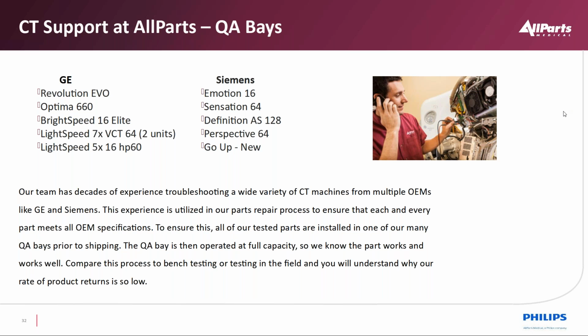And all parts are tested on a machine. We have other third parties that may test a high voltage tank, but they don't actually spin it. This is all loaded on the scanner and validated to operate on a scanner and not just on a bench test. So that is a big differentiator of what AllParts brings to the market.